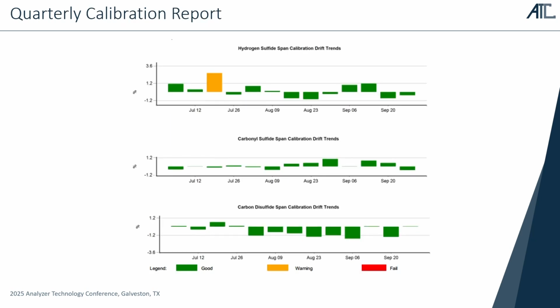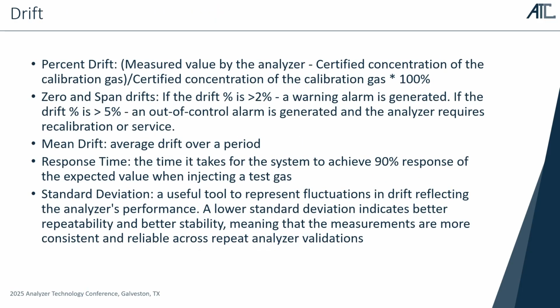And this is one illustration of a quarterly calibration report. So every day we would run a validation at each of the analyzers, and then we would generate a report that can be submitted for regulatory compliance to see when the analyzer drifted. Yellow would be warning, so that's typically 2% on this slide. If you're over 2% but under 5%, you would have a warning that you're approaching a limit. As soon as you hit 5%, you're out of control, the data becomes invalid until you recalibrate, and the out of control alarm is generated.